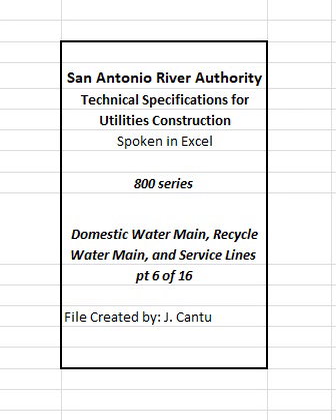U. Non-metallic pipe detection. Where non-metallic pipe is installed longitudinally, a method of detecting the location of the non-metallic pipe shall be required. Use a durable metal detection wire for non-metallic pipe detection. The specific method used shall be as approved. The materials involved shall be as specified by the manufacturer. The wire used shall be not less than 12 gauge.